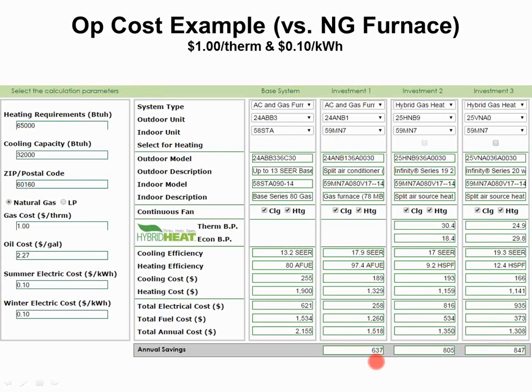People will often make that choice and say, yeah, I want to save $600 a year. I'm going to buy a new system anyway. Let's get an efficient one. If I wanted to, I could give them a hybrid system where I have a heat pump combined with that exact same furnace, right? And in that case, you're going to save $805 a year, an extra $170 over the other system. The nice thing about this software tool is it calculates the thermal break point for me.